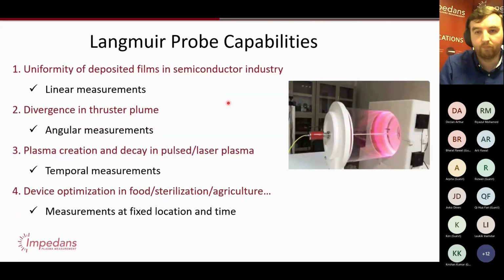In terms of capabilities, what do you use it for day to day in the field, right? So obviously for research and development. In the semiconductor industry, one of the key things is uniformity. You want to make sure that the plasma at the center of your tool is the same as at the edge. And uniformity measurements are key. And normally you do that with a waveform. But a much easier way of doing it is with a Langmuir probe with a linear drive that sweeps the probe across the surface, and from that you can measure uniformity very well and quite quickly. I'll show you some example data of that.